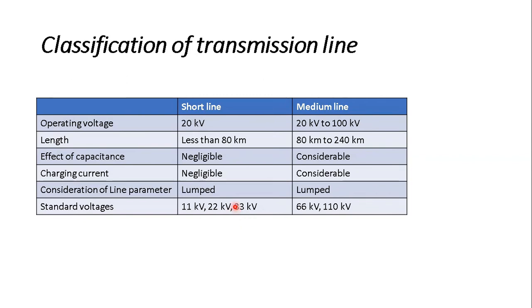A medium transmission line has a length between 80 km to 240 km and a line voltage between 20 kV to 100 kV. Due to the appreciable length and somewhat higher voltage, there is considerable effect of charging current and shunt capacitance that cannot be neglected. Although the capacitance is distributed uniformly over the entire conductor length, it is still treated as a lumped parameter. Standard voltages for medium transmission lines are 66 kV and 110 kV.